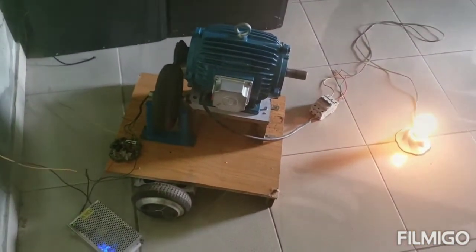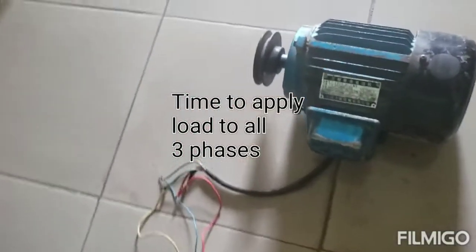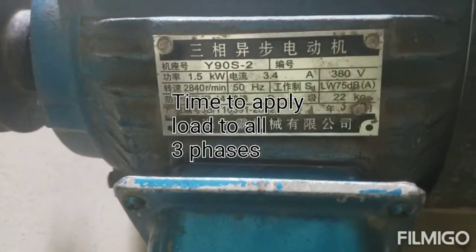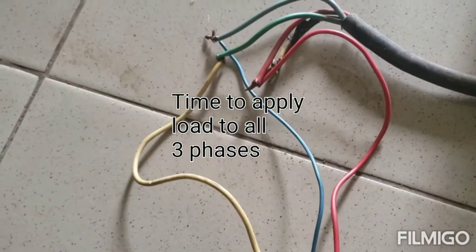I'll further increase the load. Now I'm connecting a 2 horsepower motor — it's a 3-phase induction motor. As you can see, it's 1.5 kilowatts, it's a high-speed motor: 3.4 amps, 380 volts. So I'm making use of all 3 phases that come out.